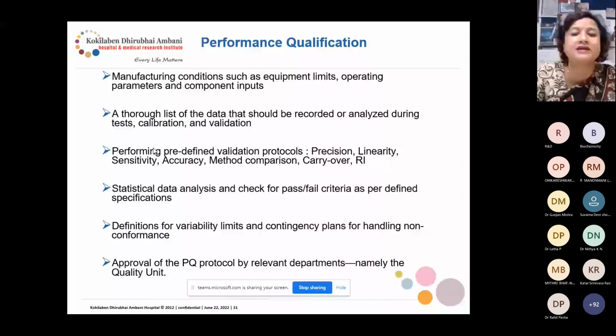Let me tell you a story. We checked everything in our lab, but during one CAP inspection, where we also participate in linearity surveys from the College of American Pathologists, one time I got a deficiency for linearity. For one of the tests, we participate in the linearity survey, so I was not bothered about the linearity check or AMR verification, analytical measurement range verification. I was very cool, and when they asked, okay, show us the linearity verification, I said, these are the linearity surveys, and we performed very well, the calibration verification, and it was linear. But then the inspector asked, when you started result reporting for the test, I said, okay, such and such date. So before that, is there any linearity survey?